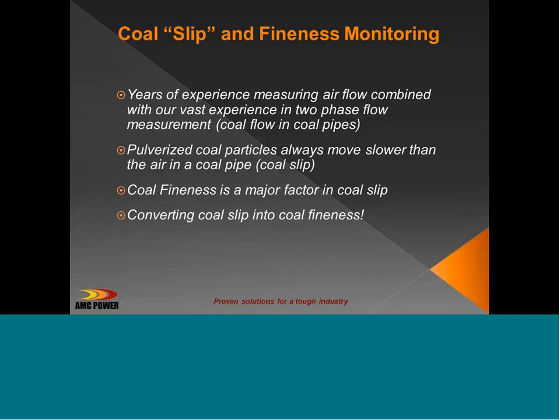In addition to coal mass flow and coal speed, one of the other things we've been working on for several years is coal fineness monitoring. What we know from years and years of measuring combustion airflow, and now with our new experience with coal flow measurement and 2-phase flow, we've learned a lot about the relationship between the air and the fuel. We know the coal particles will always move slower than the air in a coal pipe, and we also know that the coal particle size is one major factor in that slip factor.